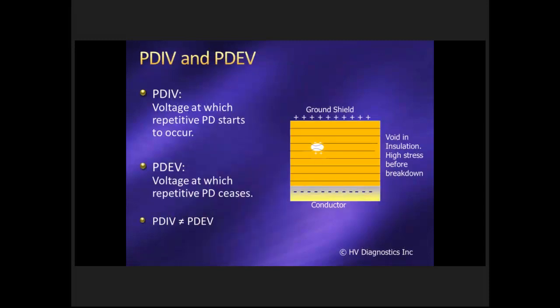So if we look at partial discharge inception voltage, as I mentioned earlier, you have to bring up the voltage, and at some point you will find that PD will take place. That's called the inception voltage. And if you look at this diagram on the right over here, what happens if you take a classical void in insulation, you get constant field lines, but because of the difference in permittivity, basically the property of the air versus that of the outside insulation, you get a concentration of electric fields inside that void. And as that electric field strength gets higher than what the air can actually take, you get a breakdown that takes place.